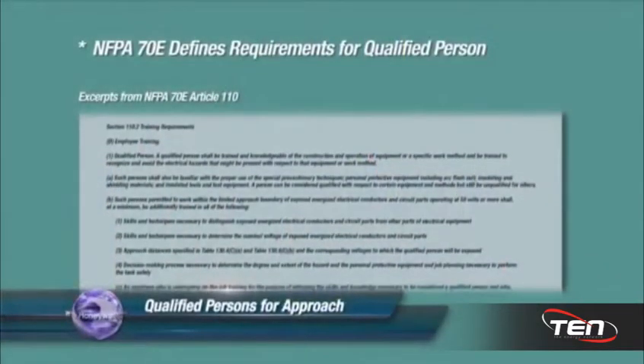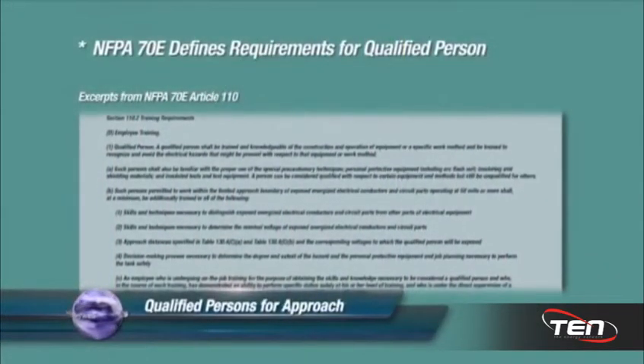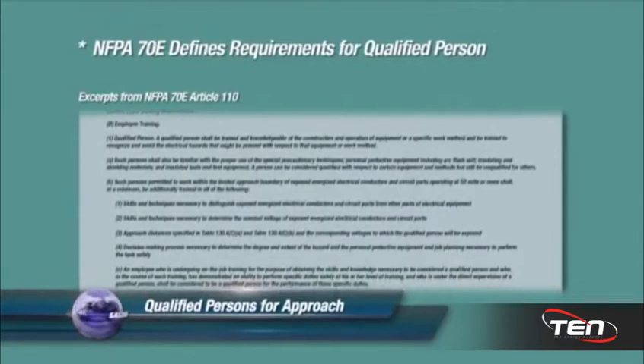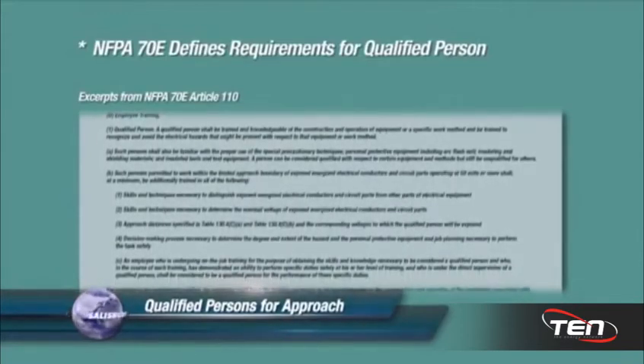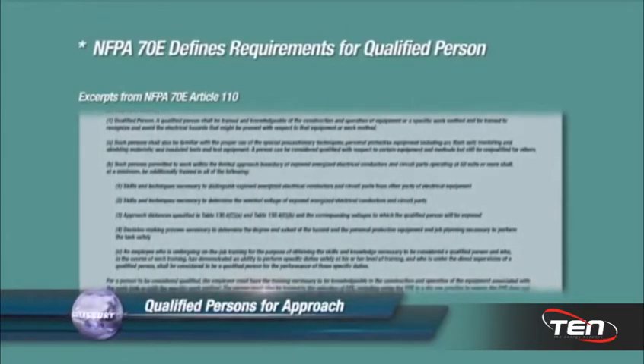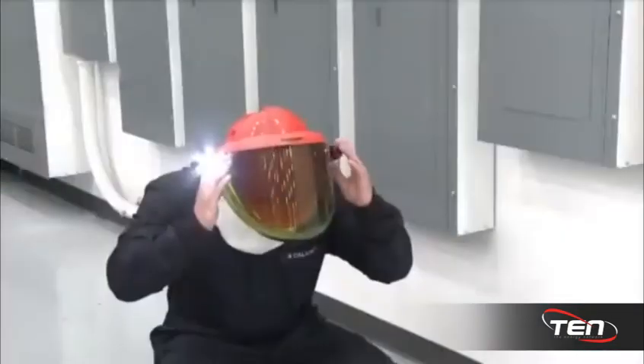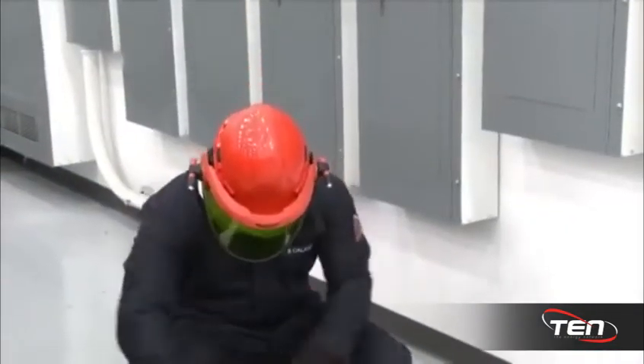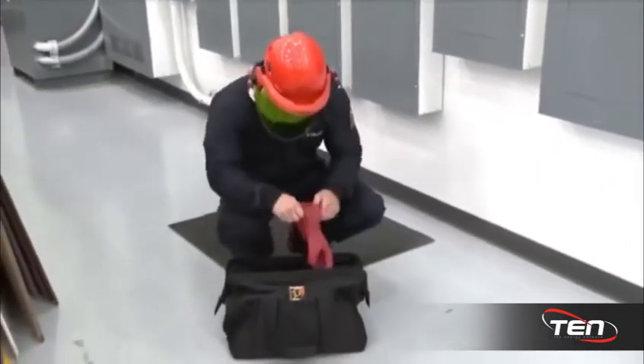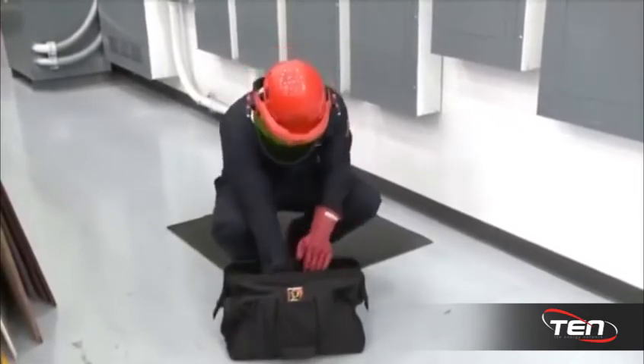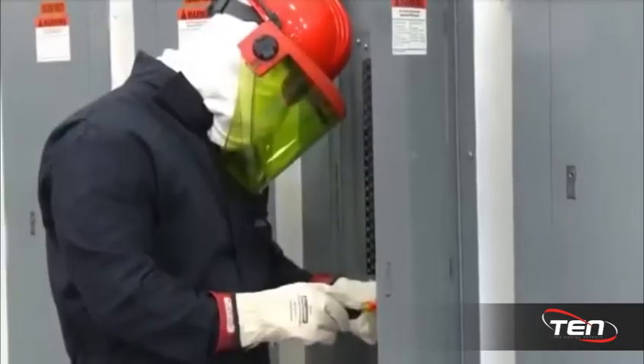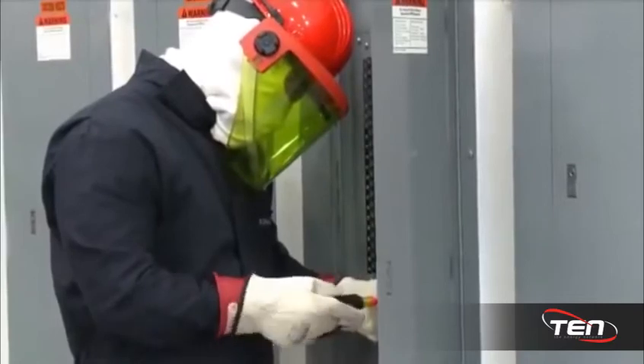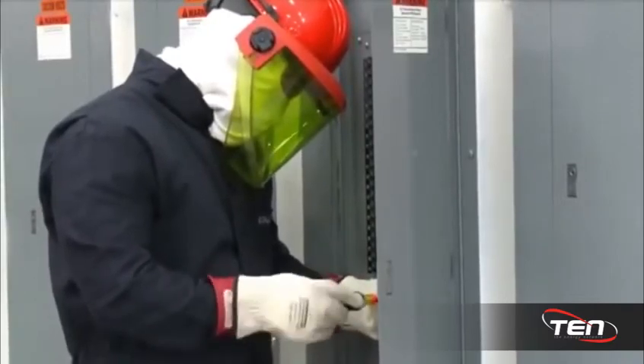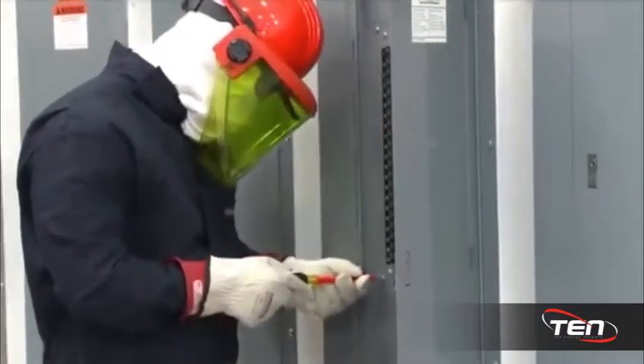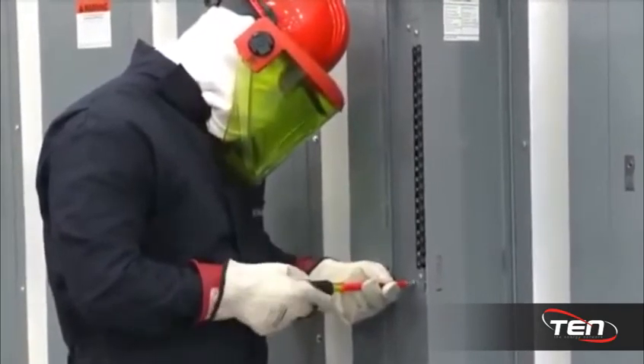The NFPA 70E standard defines the requirements for being a qualified person. Complete adherence to the information given in the NFPA 70E standard is critical to arc flash safety. In fact, with proper PPE combined with knowledgeable employees, the risk of an arc flash can be greatly reduced. The next step is to determine your hazard risk category or calculate the exposure you might face in the field. NFPA 70E offers two methods.